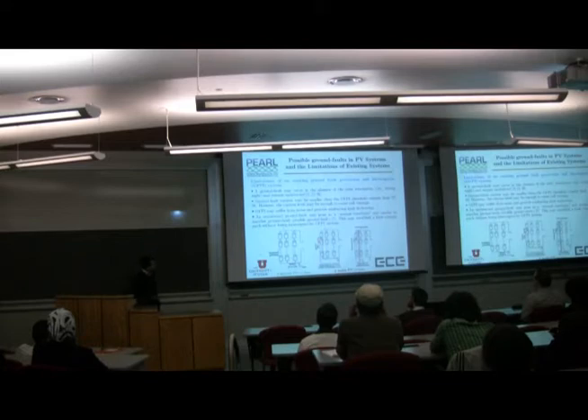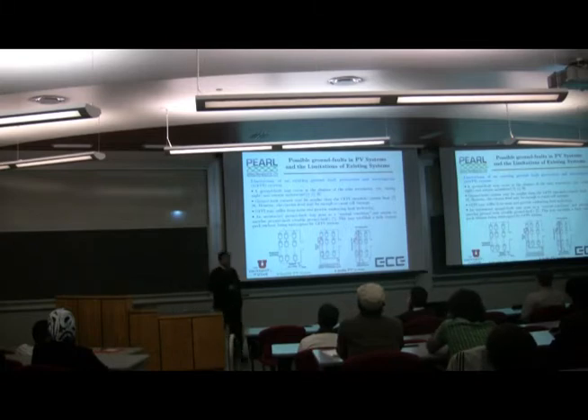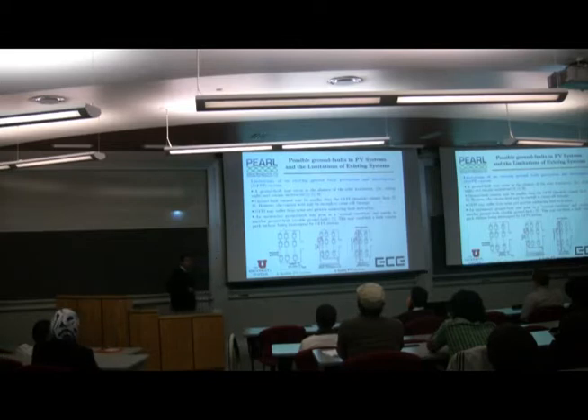So what can be done? Either we have to use a very smart GFDI system that is very sensitive, but there is actually a penalty for doing that. If you make the GFDI very, very sensitive, then it suffers from noise and provides misleading fault indications, and I have seen it.